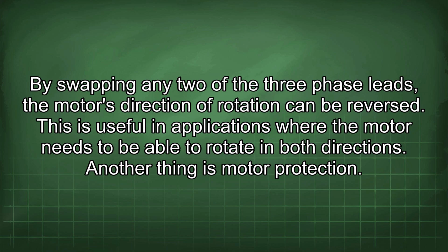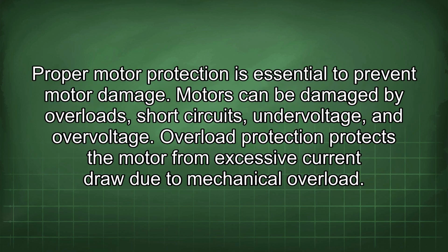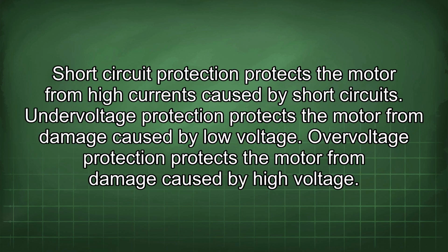Another thing is motor protection. Proper motor protection is essential to prevent motor damage. Motors can be damaged by overloads, short circuits, undervoltage, and overvoltage. Overload protection protects the motor from excessive current draw due to mechanical overload. Short circuit protection protects the motor from high currents caused by short circuits. Undervoltage protection protects the motor from damage caused by low voltage. Overvoltage protection protects the motor from damage caused by high voltage.